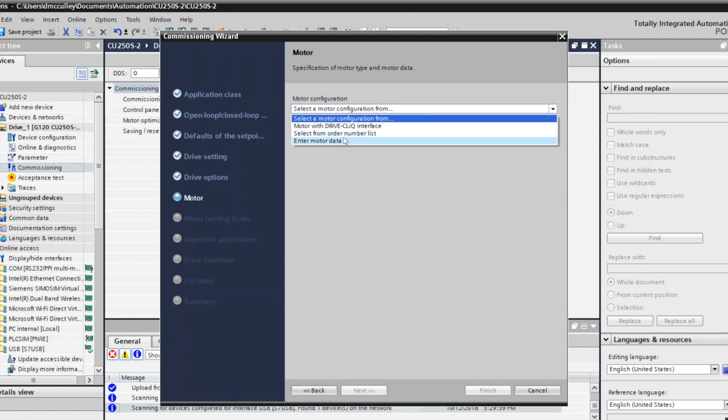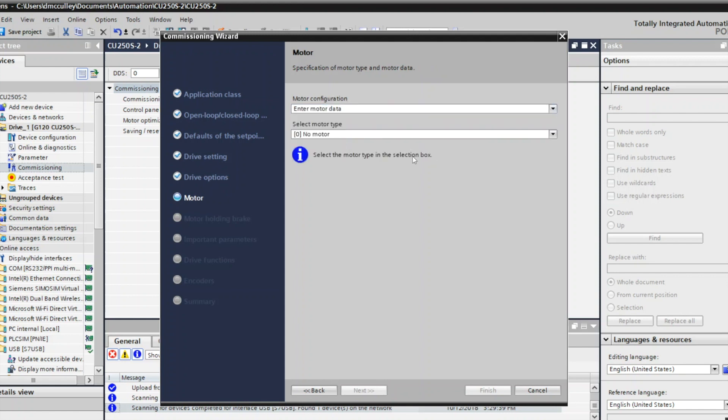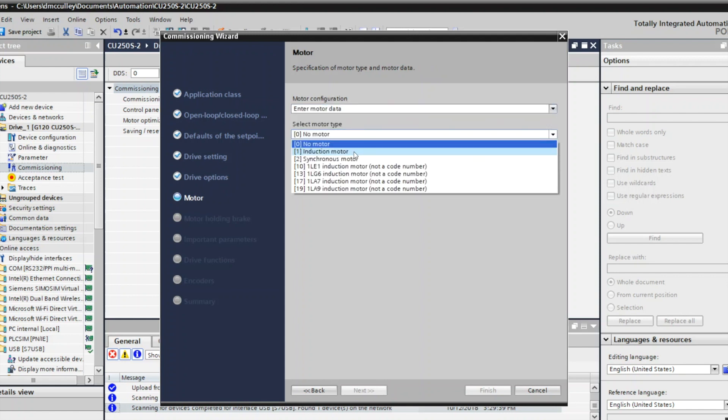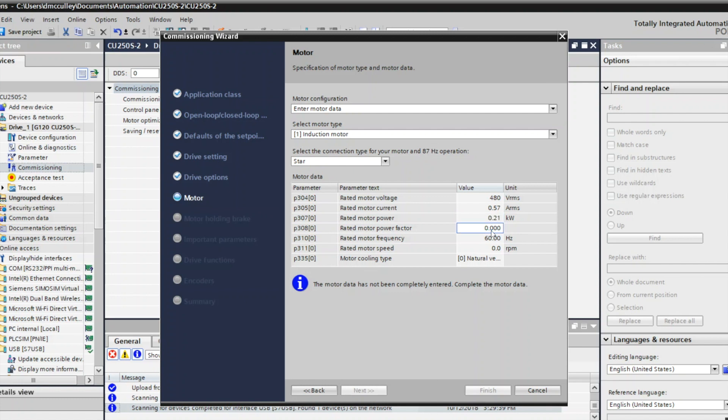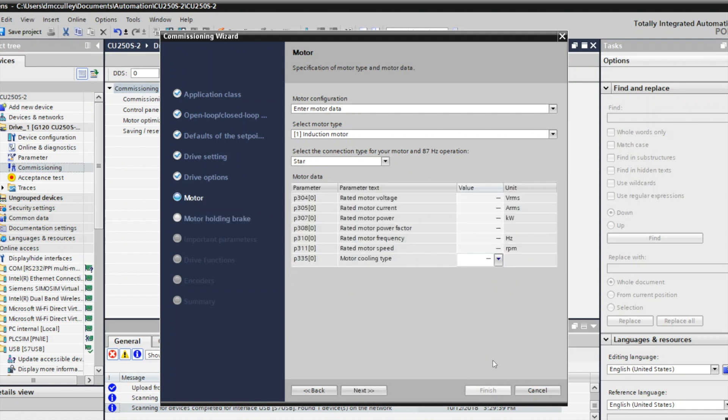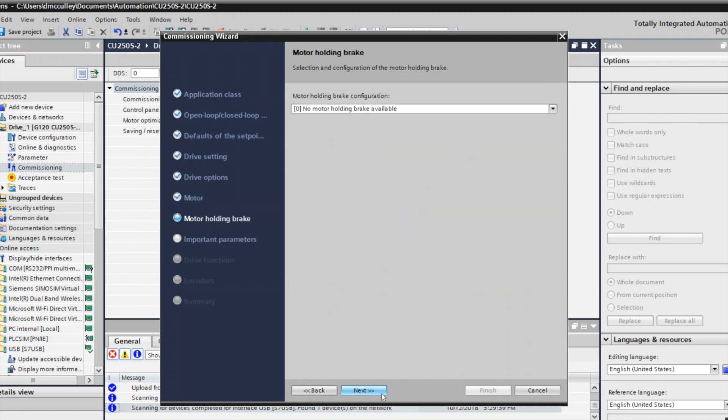Now I can choose to enter my motor data. I have an induction motor. My rated motor current is 0.57 amps, 0.21 for the kilowatts, 0.75 for the power factor, and 1650 for the speed. Click next.